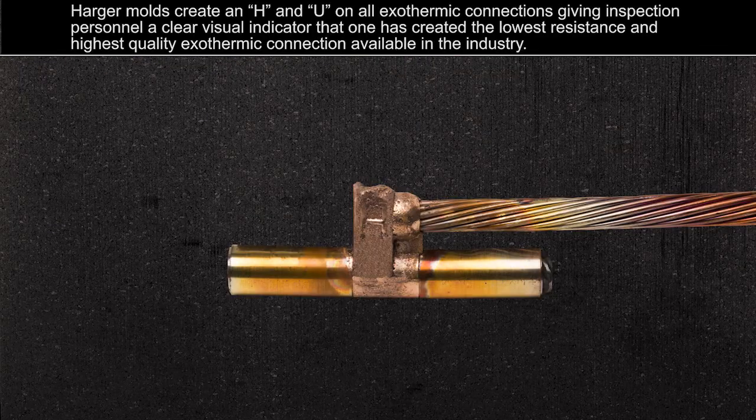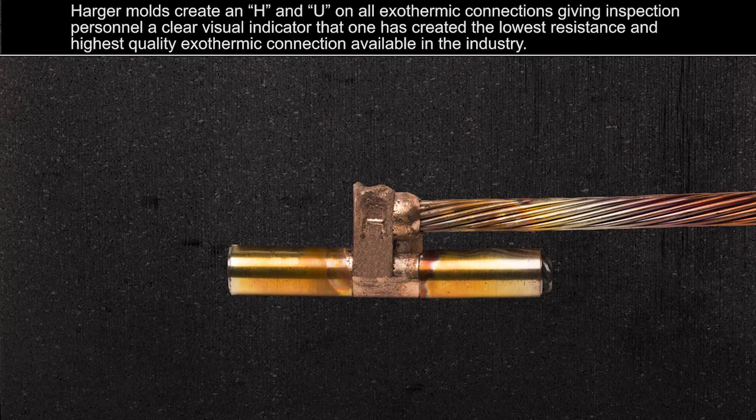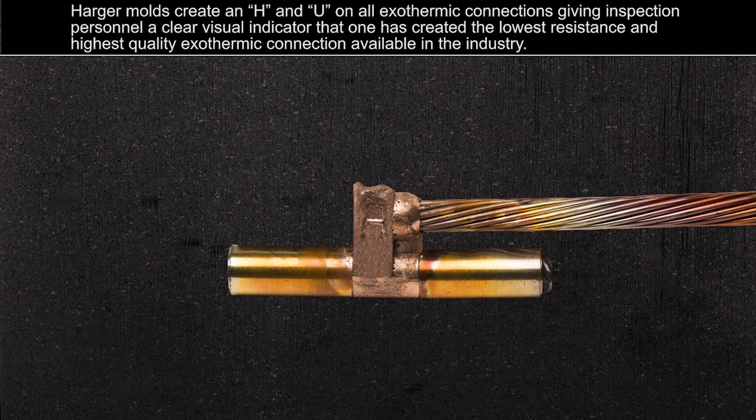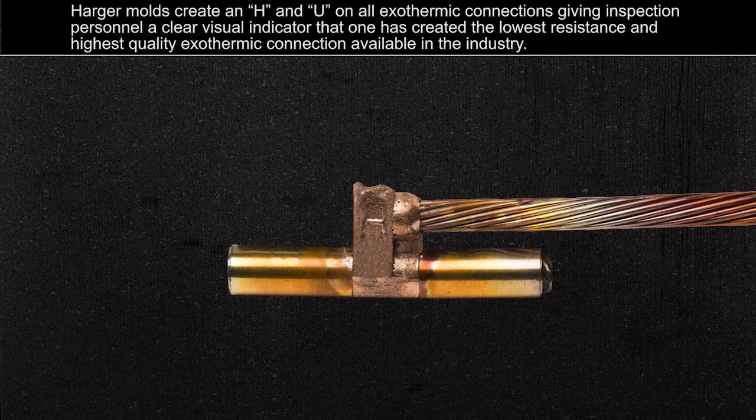Harger molds create an H and U on all exothermic connections, giving inspection personnel a clear visual indicator that one has created the lowest resistance and highest quality exothermic connection available in the industry.